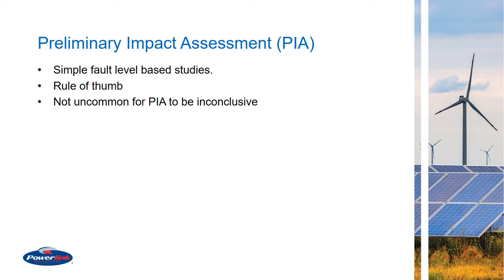Preliminary impact assessment, which is PIA, is a very simple fault level based study, and these are basically used as a rule of thumb to decide whether detailed assessment or full impact assessment is needed or not. And the point that I would want to highlight here is it's not really uncommon for a PIA to be inconclusive, hence needing the full impact assessment.